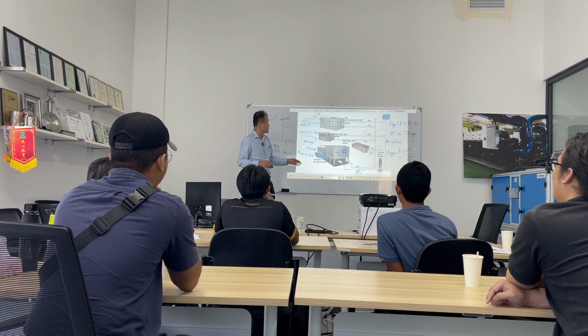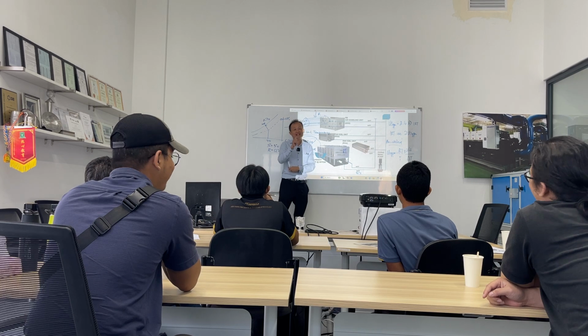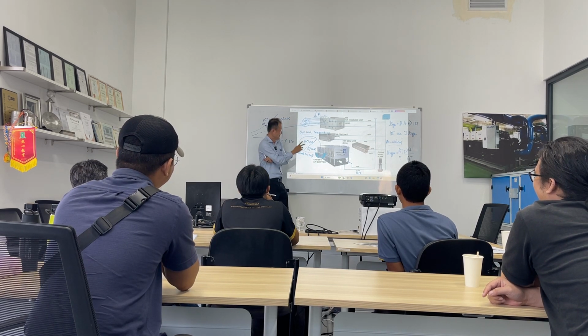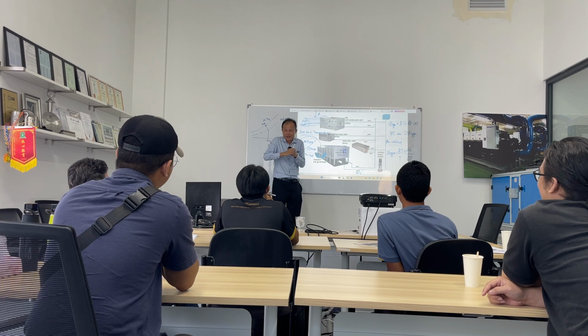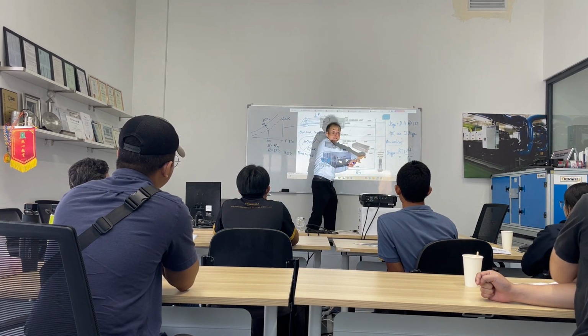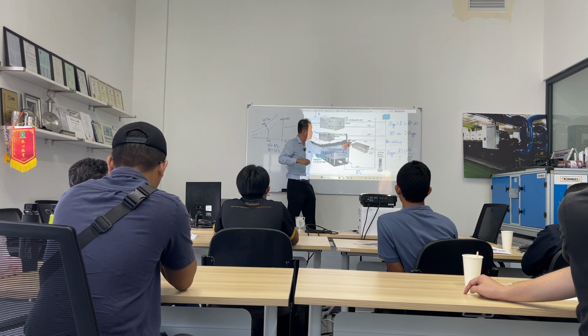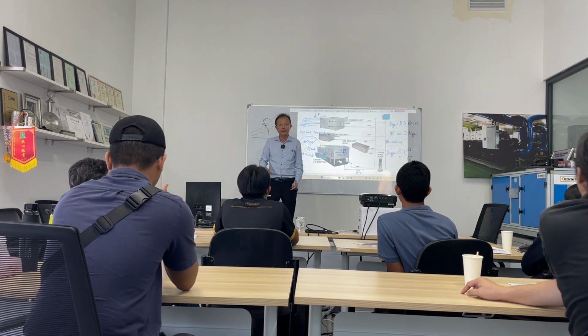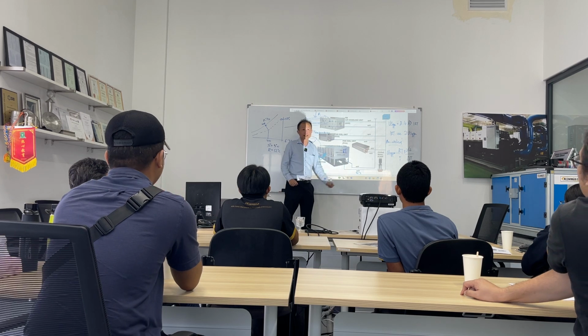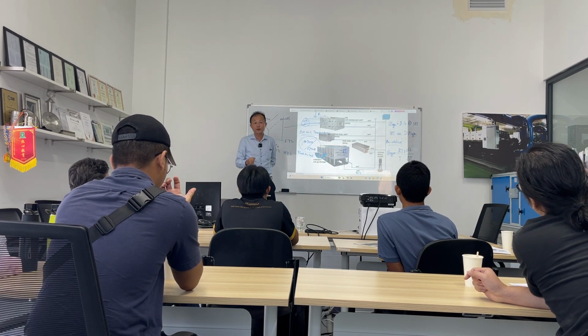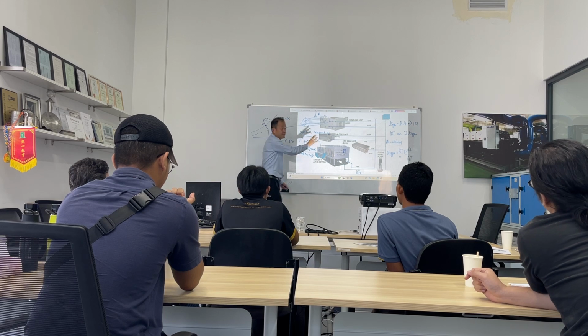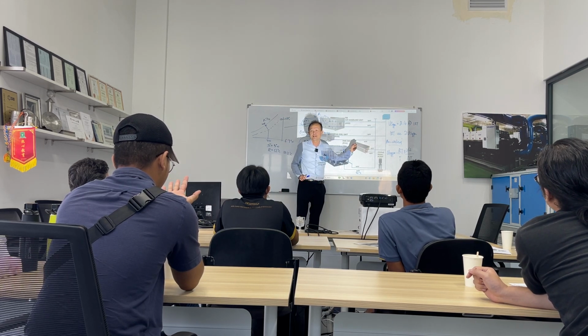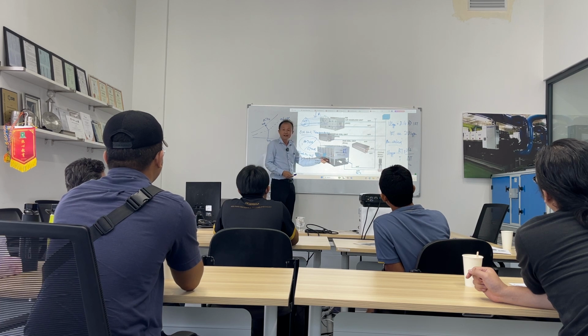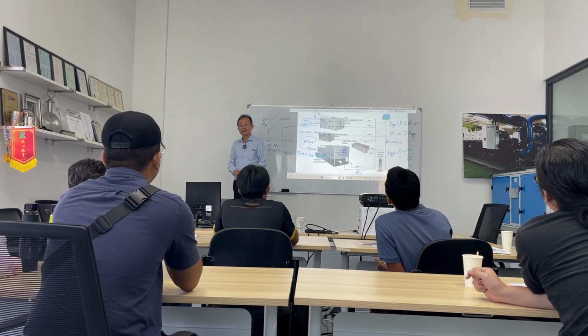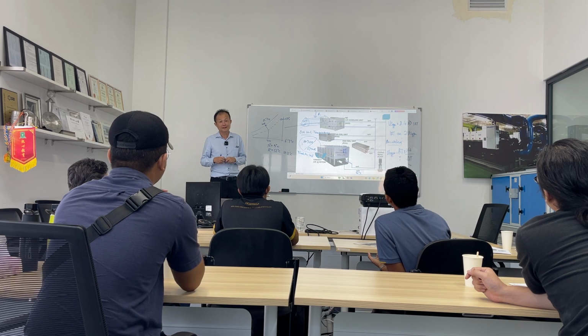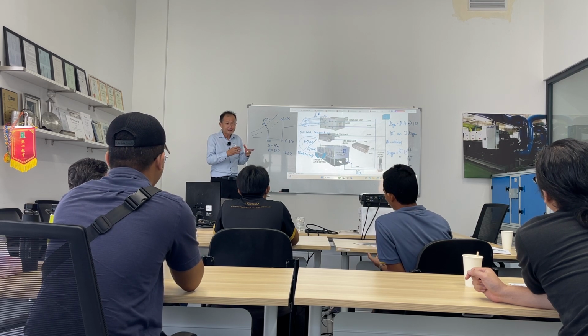Understand? So, like I say, when the system is increasing in size and the chiller plant room is further away from the system, with a lot of long piping, it's worth considering this higher delta T, because the piping cost is very high when the pipe is long. So all this saving can almost quite certainly more than compensate for the penalty that you face here. So is it good to learn new things like this?